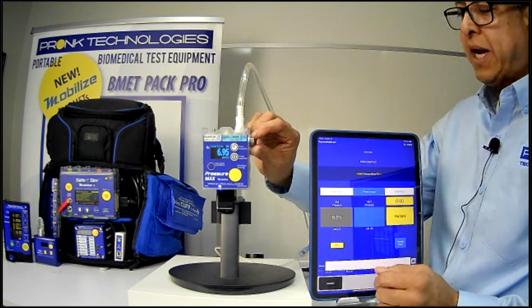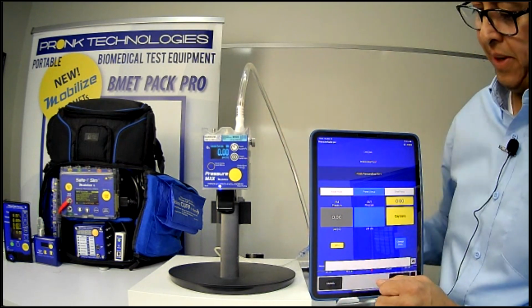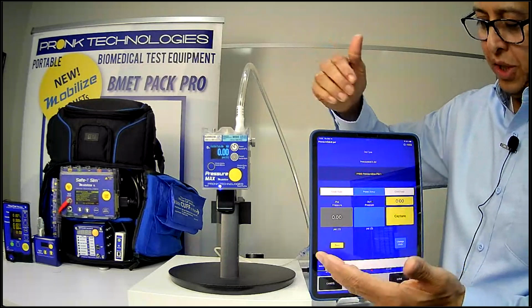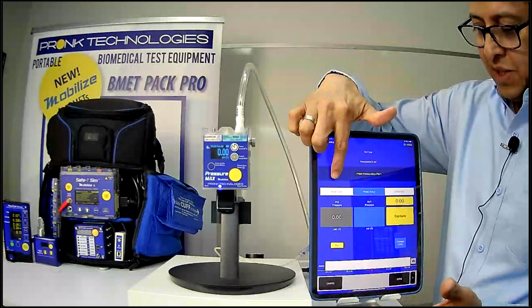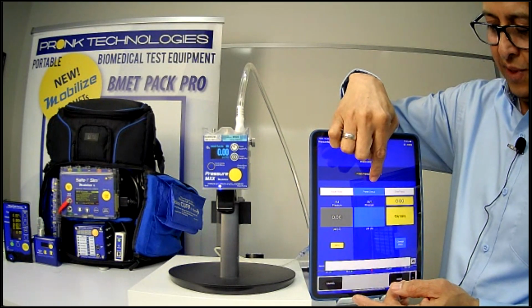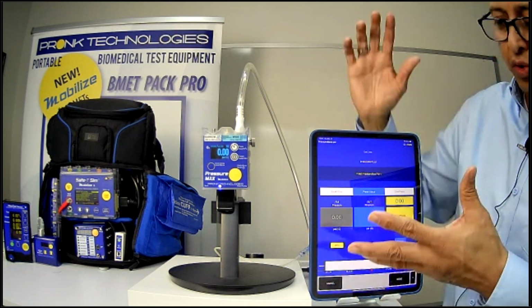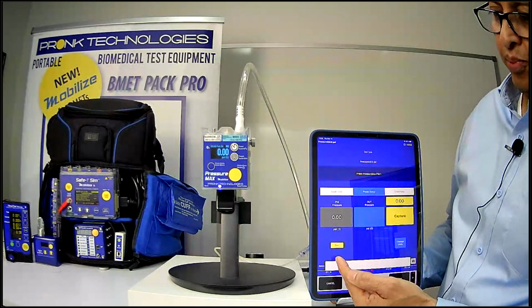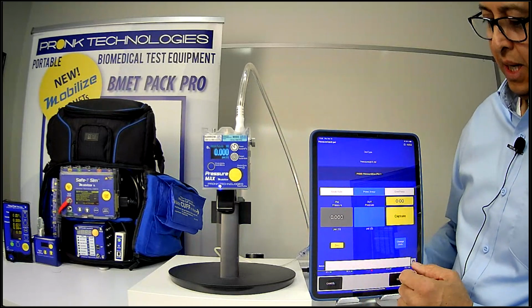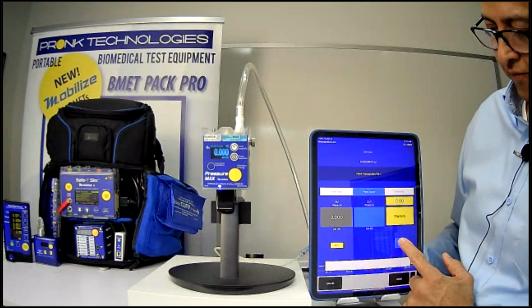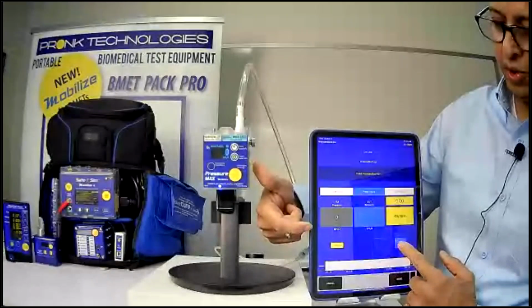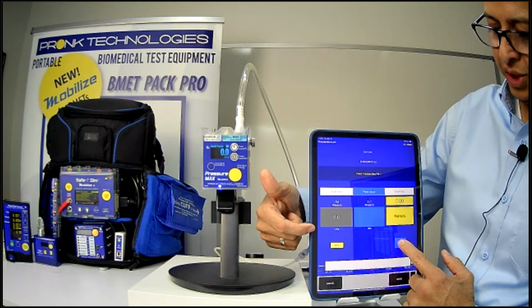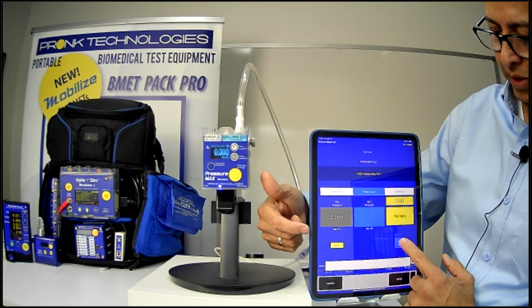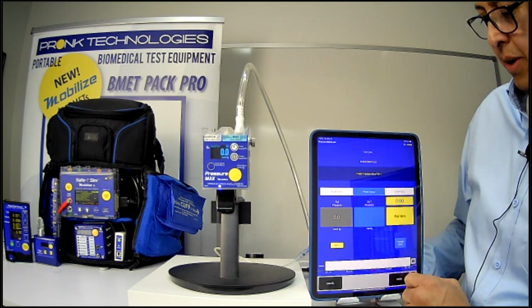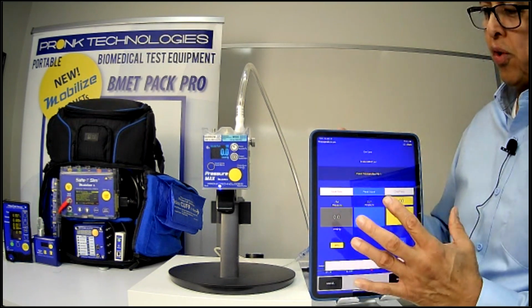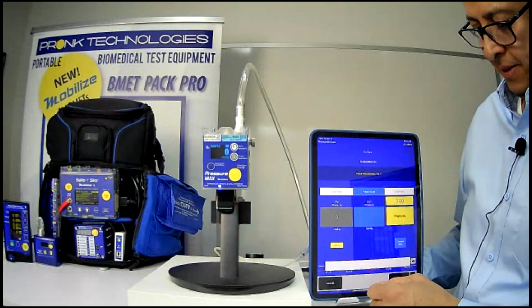So the way it's set up, and I'll go ahead and release the pressure so we can start from the beginning, is you have a menu option here which you can utilize to do a leak rate test if you need to. You could do a pressure accuracy test if you're checking pressure, verification of pressure, you're doing a calibration or adjustment. I could zero the pressure transducer from the Pressure Max from here. And I can also change the units of measure from here as well. So if I want to do it in a different unit of measure, you'll see here on the left, the unit of measure changes. So I'm able to select any unit of measure I want. So I'm going to go ahead and just select millimeters of mercury. So I am in control of the Pressure Max from the Mobilize app, and I'm able to do some tests.